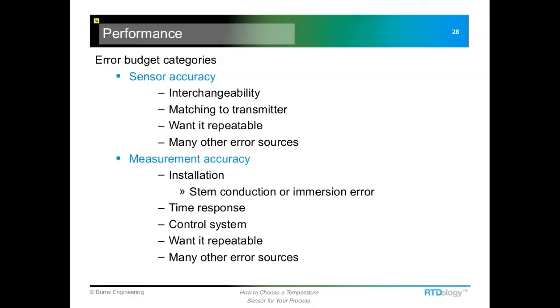The RTD probes are generally very accurate. You can get it right out of the box with like plus or minus 0.13 degrees C at 0. And then you might stick it in a process that's got some problems, and you may end up with plus or minus 5 degrees as your measurement accuracy. So we're going to look at where those errors come from, how to minimize them, and how to get within our 1 degree Fahrenheit budget that we set at the beginning of this presentation.